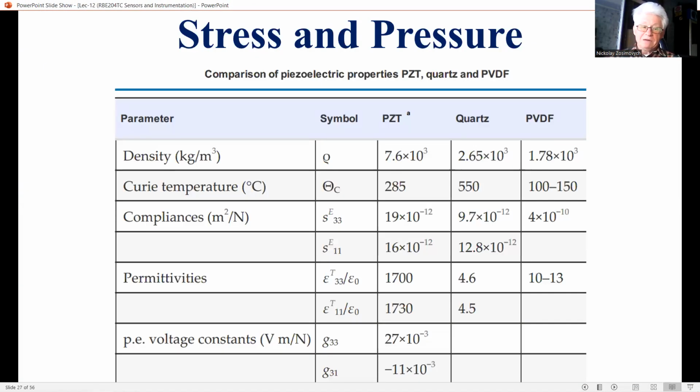Uniaxially stretched and poled PVDF shows a rather strong piezoelectric effect. Let's look at this later. A straightforward design of a pressure sensor using this property is a sheet of PVDF on top of a rigid backing, making use of lateral deformation. However, the flexibility of PVDF allows the material to bend easily, so it can serve as a membrane, resulting in a much higher pressure sensitivity.